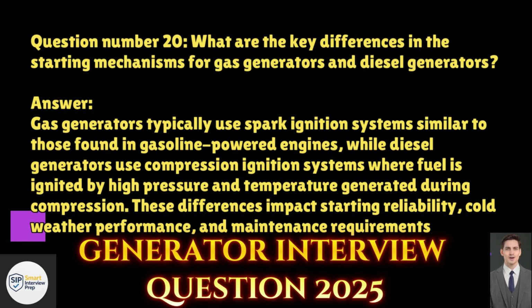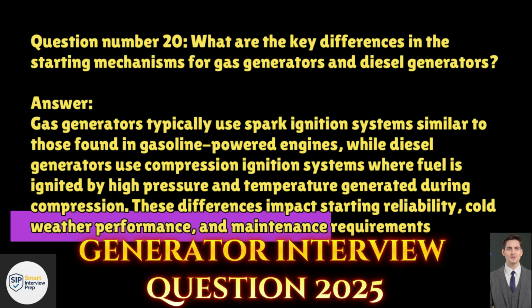By comparing these factors over the expected lifespan of the generator, you can determine which option offers the best value for your specific application. Question 20: What are the key differences in the starting mechanisms for gas generators and diesel generators? Answer: Gas generators typically use spark ignition systems similar to those found in gasoline-powered engines, while diesel generators use compression ignition systems where fuel is ignited by high pressure and temperature generated during compression.